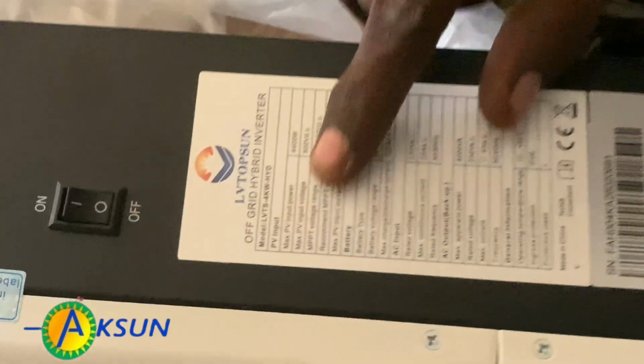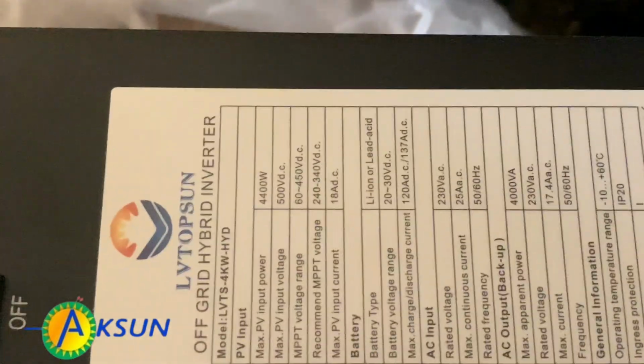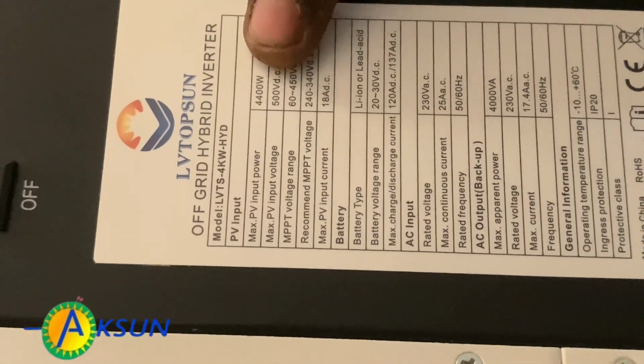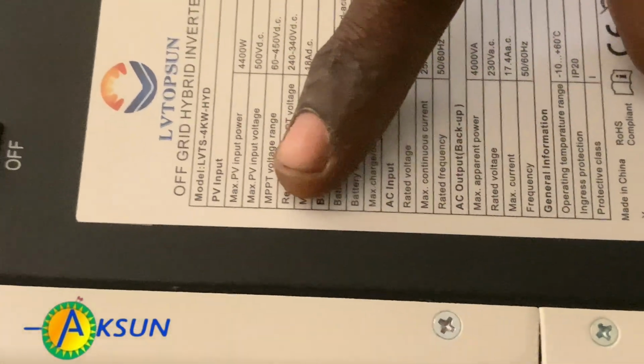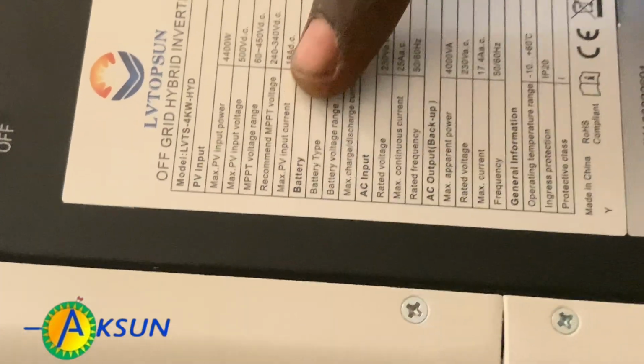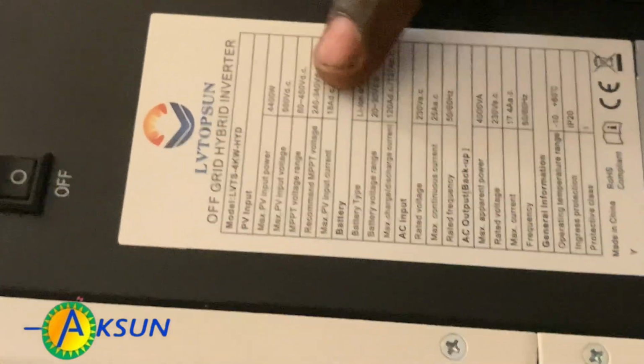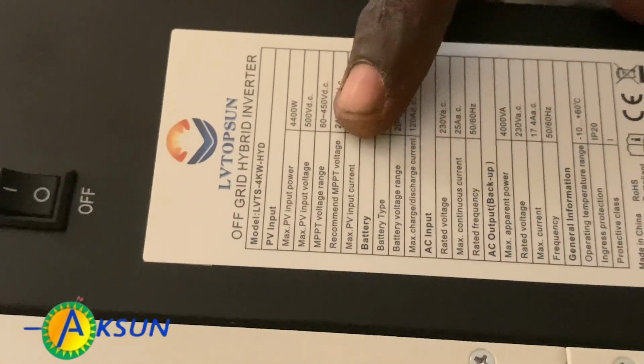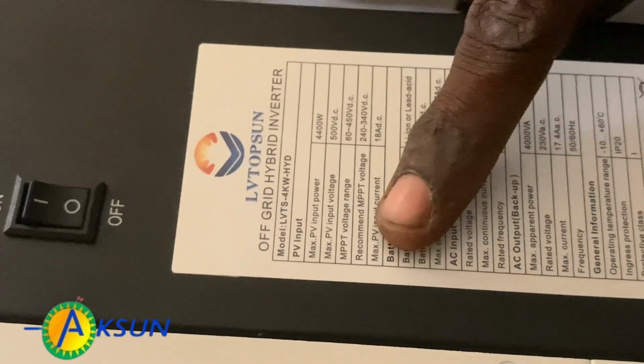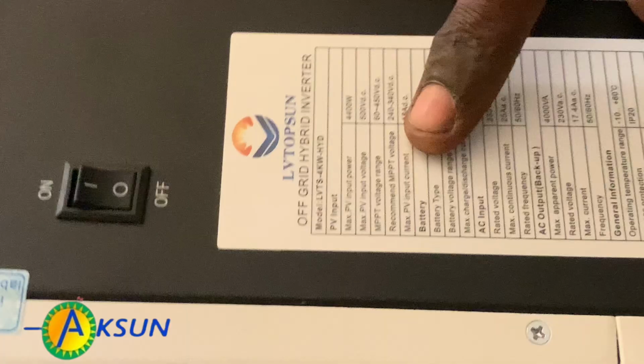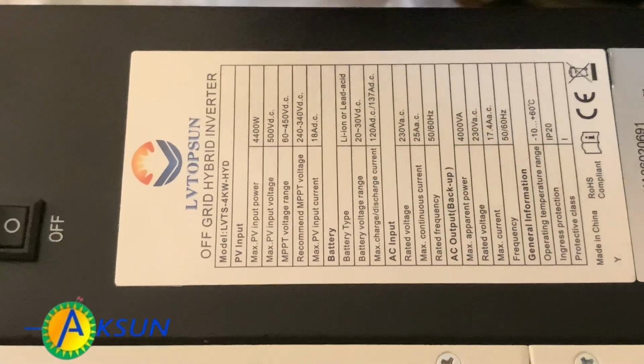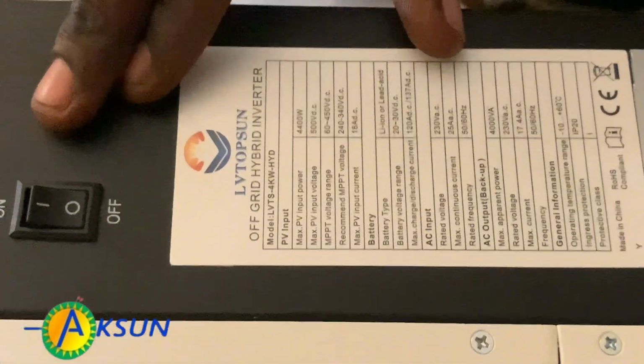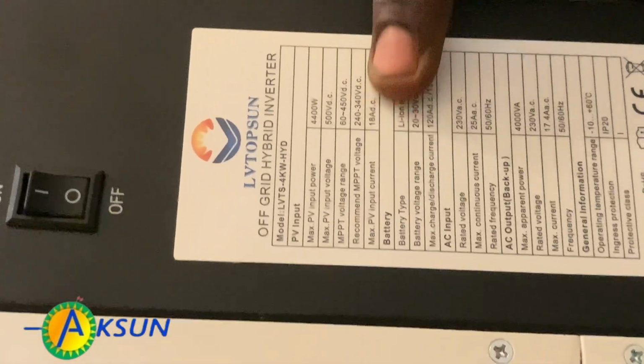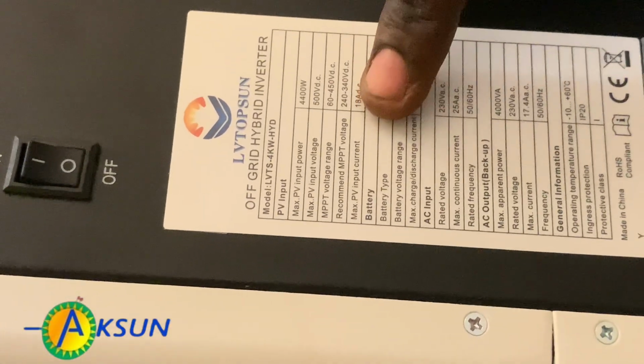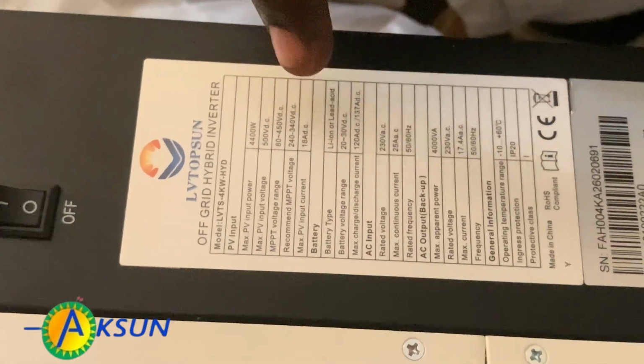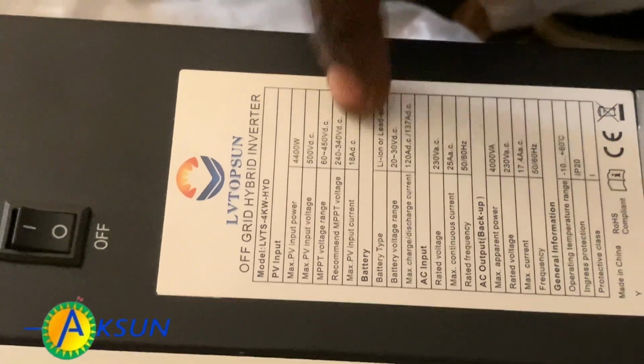Now you can see max PV is 4400. The inverter itself is 4000 watts, but we can push in as high as 4400. The PV input max is 500 volts. Then the voltage range, this is what I always specify about, the best voltage range, make sure you work within that range: this is 60 to 450. Now the recommended range is most important: no matter your solar panel configuration, you must work within this recommended voltage, pushing between 240 to 340 volts for the best charging of the system.